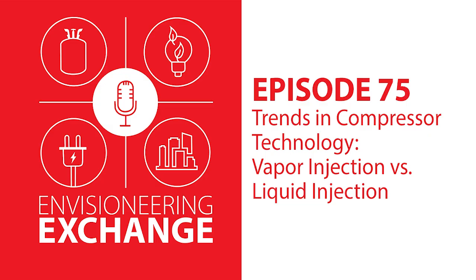The reason for that is, as you subcool the liquid further coming out of the economizer, the quality going into your evaporator is lower. So you get more benefit there as far as the capacity goes. On the efficiency side, as you're injecting this intermediate pressure vapor into the compressor, you have your low pressure and your high pressure, which is standard on every compressor. But when you have the intermediate portion, you can actually adjust the compression. The compression ratio of the compressor changes, and you get a little bit more efficiency as well. It also comes with the ability to cool the motor down and expand the operating map of the compressor to run at super low temperatures.